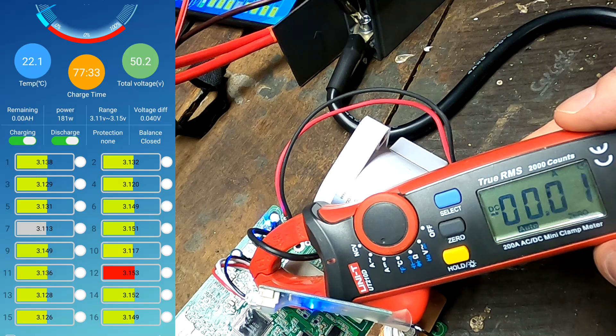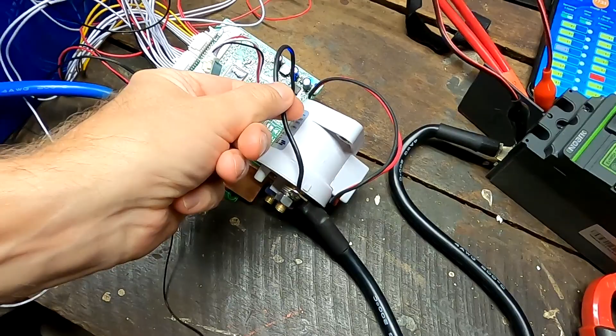Well, it looks like I was a bit wrong. Probably have a bad memory, but I could swear I measured around 800 milliamps going through this cable when the relay was turned off. Obviously I was totally wrong, there's almost no current going through this black cable. If the relay is turned off, there's only 30-35 milliamps going into the BMS here. It comes out because this is a negative. As soon as the BMS recognizes these 35 milliamps, it turns on the relay again to charge the battery in a low voltage disconnect situation.